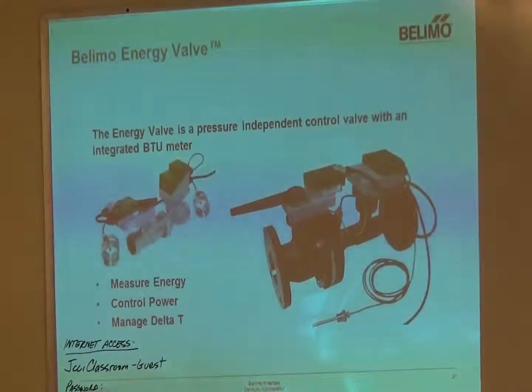Well, as we were saying, we can measure the energy with these valves, control power, manage delta T, and you basically have an integrated BTU meter. Now, I've been told by some contractors that using this valve costs less than some of the BTU meters that are on the market. I've had people tell me that they're not even using the valve for all its functionality. They buy it as a BTU meter at times. We recommend, of course, that you use the valve to its full capabilities, but I just wanted to put that out there that it is a nice BTU meter as well.